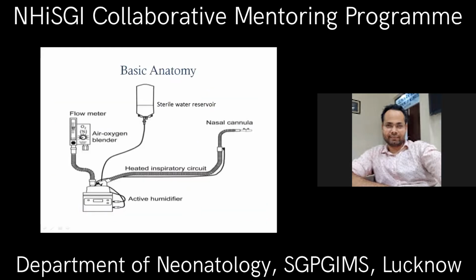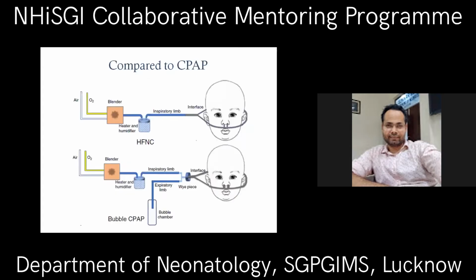So the basic anatomy is that there is a flow meter or flow generator device, and there should be an air and oxygen blender source, which is connected to the humidifier, which is filled with a sterile water reservoir, and this in turn is connected to the heated inspiratory circuit, which is attached to the nasal cannula of the high flow device. Compared to CPAP, we can see that there is a single limb circuit. Only an inspiratory limb is present, and it is an open system. In CPAP, there is an expiratory limb connected by a Y piece, which leads to a closed circuit. And we can see the nasal prong sizes are also small in HFNC.